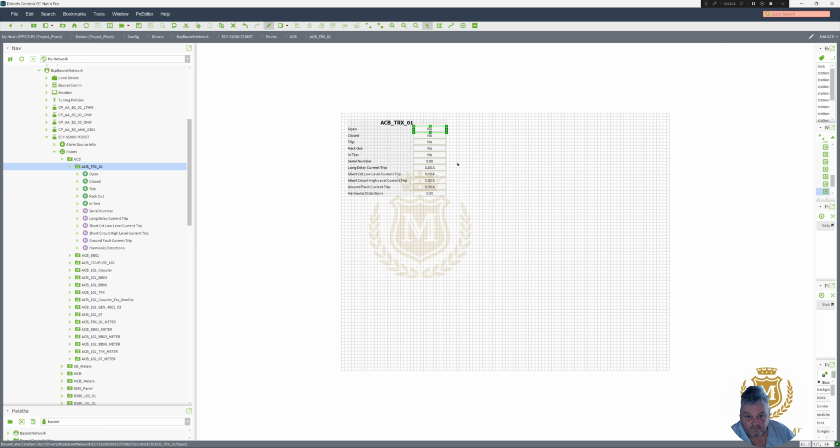And then these ORDs want to be relativized. So we just click on that, and that does it all for us automatically. So if we look into one of them ORDs now, that's my open slot, that's my closed slot. And then we need to do some graphics as well, but this page is too big at the moment for pop-up, so let's just minimize it to say 600 by 400 just for the moment. But whatever we change on this graphic now will be for all those ACBs.